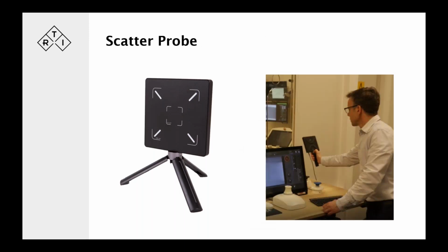We talked about the scatter probe. It comes with a built-in stand that collapses, and it can be used as a holder or a handle if you want to do some form of survey measurement or move the probe, for instance, behind a lead glass, or look at leakage through door jambs or edges of the lead glass and into the controller area.